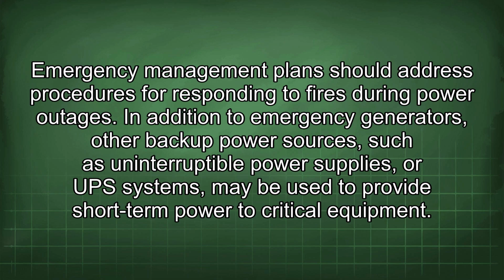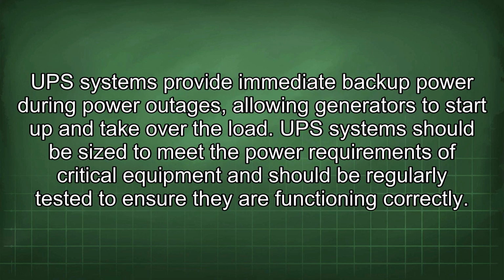In addition to emergency generators, other backup power sources such as uninterruptible power supplies, or UPS systems, may be used to provide short-term power to critical equipment. UPS systems provide immediate backup power during power outages, allowing generators to start up and take over the load. UPS systems should be sized to meet the power requirements of critical equipment and should be regularly tested to ensure they are functioning correctly.